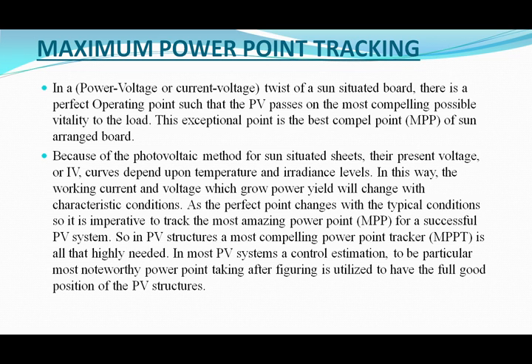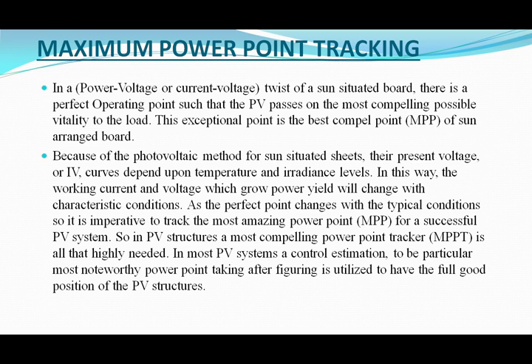Now, maximum power point tracking. In this, the power-voltage or current-voltage characteristics of a solar panel have a perfect operating point such that the PV delivers the most possible energy to the load. This exceptional point is the maximum power point of the solar panel. Because of the photovoltaic effect, for solar panels, the current-voltage or I-V curves depend upon temperature and irradiance levels. Therefore, the operating current and voltage that maximize power yield will change with environmental conditions. Since the optimal point changes with these conditions, it is imperative to track the maximum power point for an effective PV system.